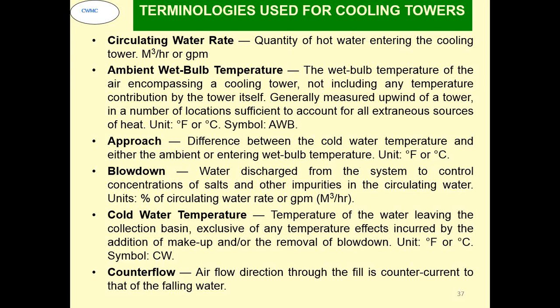Approach. This is the difference between the cold water temperature and either the ambient or entering wet bulb temperature. Unit is again degree Fahrenheit or degree centigrade. Blow down is that water which is intentionally taken out from the system to maintain the concentration of various salts in the system. It is again measured in terms of circulating water. It is measured in terms of either meter cube per hour or gallons per minute. Cold water temperature, it is the temperature of the water leaving the collection basin, exclusive of any temperature effects incurred by the addition of makeup and or the removal of blowdown. Units are again degree Fahrenheit or degree centigrade.